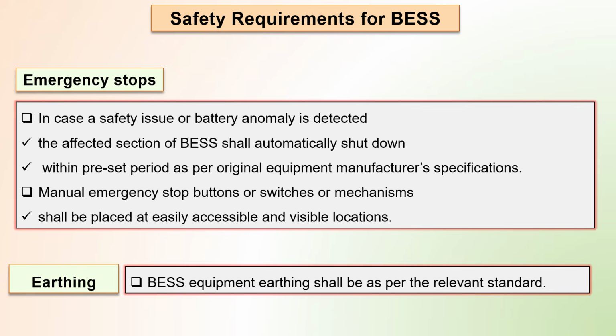Thereafter, there shall be a provision of emergency stops. In case a safety issue or battery anomaly is detected, the affected section of BESS shall automatically shut down within a preset period as per original equipment manufacturer's specifications. Then manual emergency stop buttons or switches or mechanisms shall also be provided at easily accessible and visible locations. There shall also be earthing provisions as per the relevant standard.